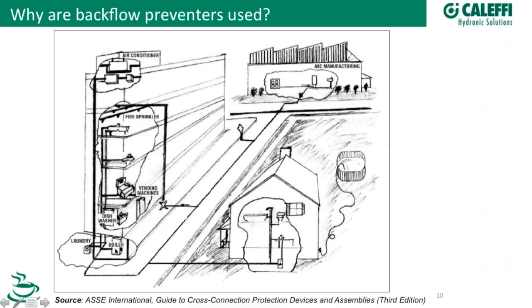On the top, you might have air conditioning or chiller, and you may have some open tanks. You're either going to need air gap separation or ASSE 1013 — referred to as RPs — to contain that high hazard. If it's an open vat, there can be all kinds of pollutants, even vermin or birds — all kinds of undesirable things that nobody wants associated with their drinking water. So this illustrates different levels of customers being served and how we've got to protect against our pressure being overcome or reduced.